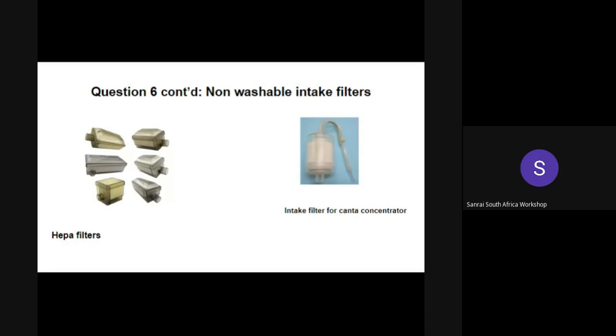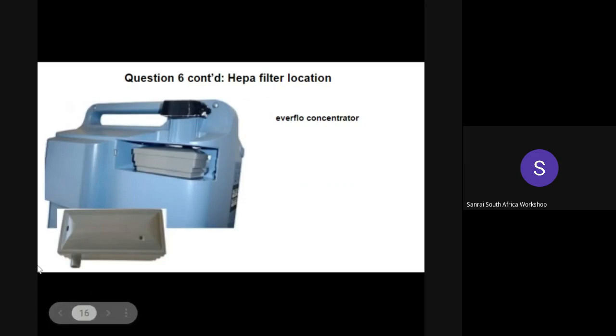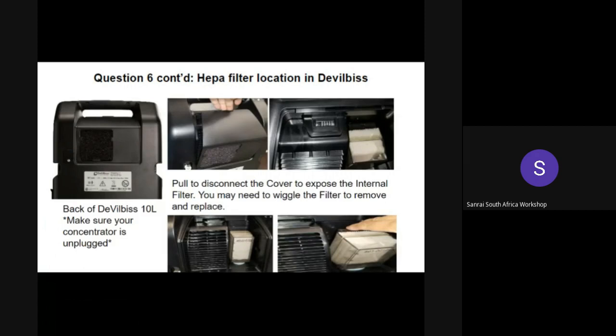The intake filter is connected to the compressor intake and traps dust particles that may have passed through the cross-particle filter. It also acts as a noise dampener for the compressor. Some concentrators like the AirSep and the J5 have washable intake filters that can be washed the same way as the cross-particle filter. Concentrators like the DeVilbiss use non-washable HEPA — High Efficiency Particulate Air — filters that should be replaced when visibly dirty. The Canta concentrator has a non-washable intake filter that can be opened like a bottle to blow out accumulated dirt, then replaced when it can no longer be reused.